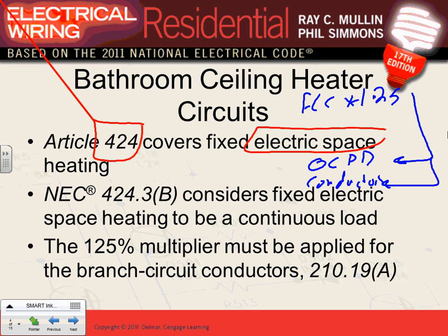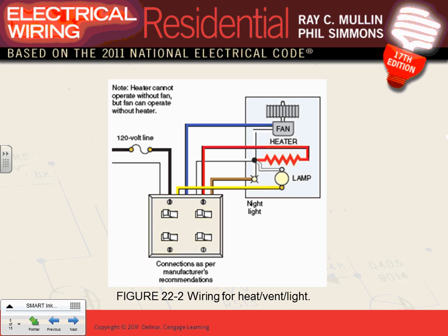Control, typically they're built-in control. They're built-in control with these equipments. Here's where it says why we multiply by 1.25, because it's continuous load, right? That's exactly what we summarize here. It's a continuous load, and since it's continuous load, we size it based on 1.25. Can I have thumbs up, guys, for the heater? That's for my heater. Okay, here's the combo, though.